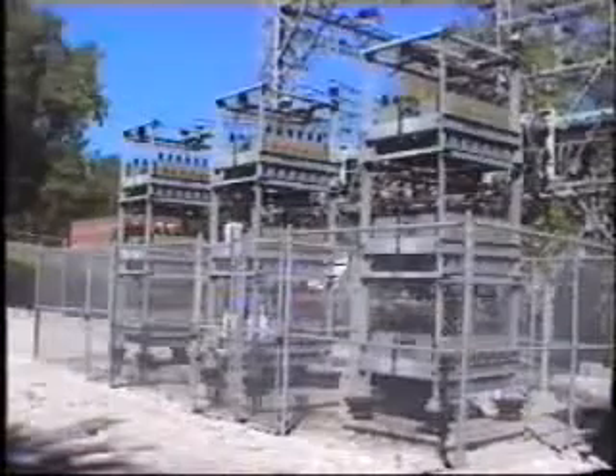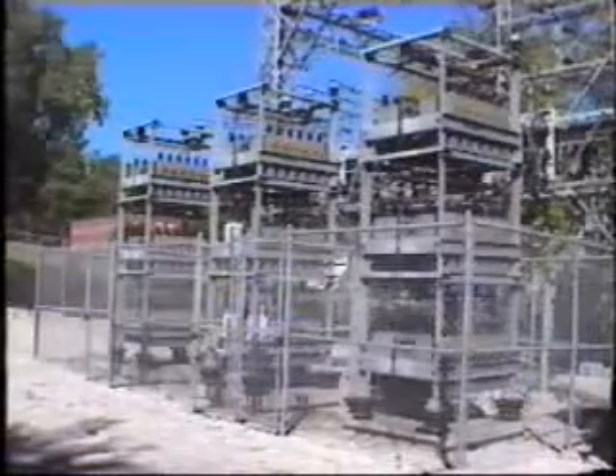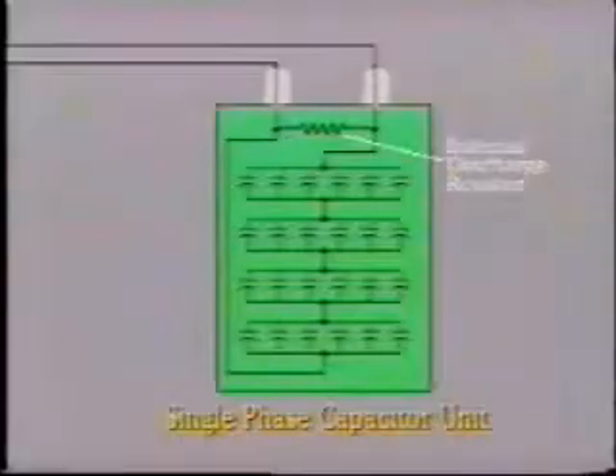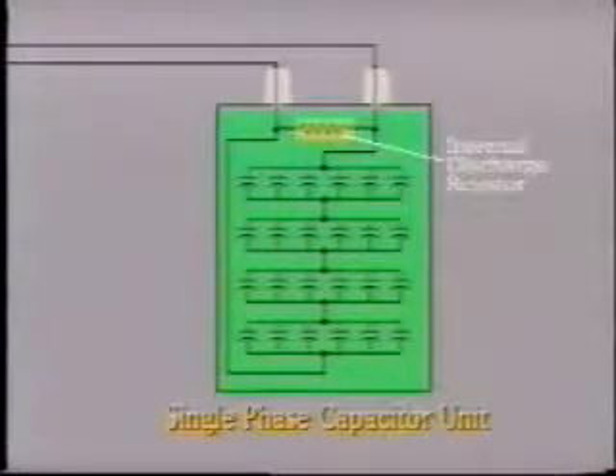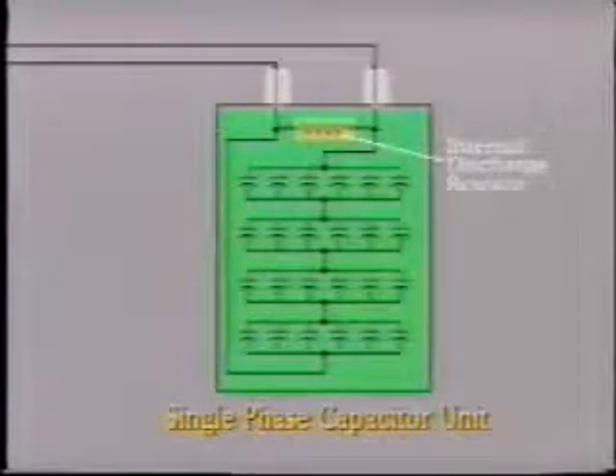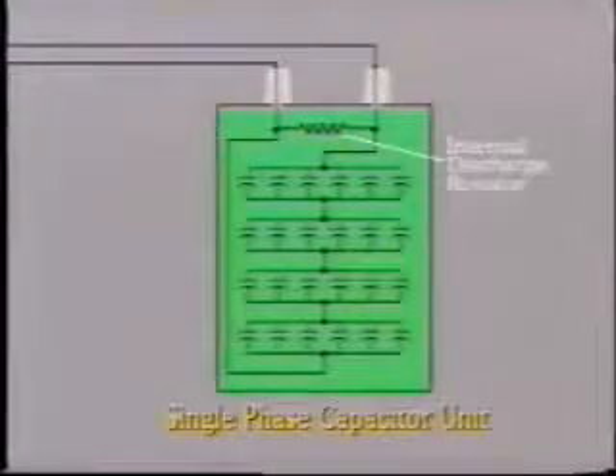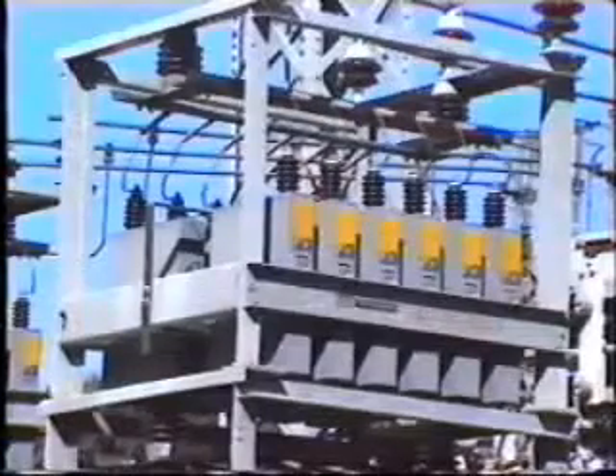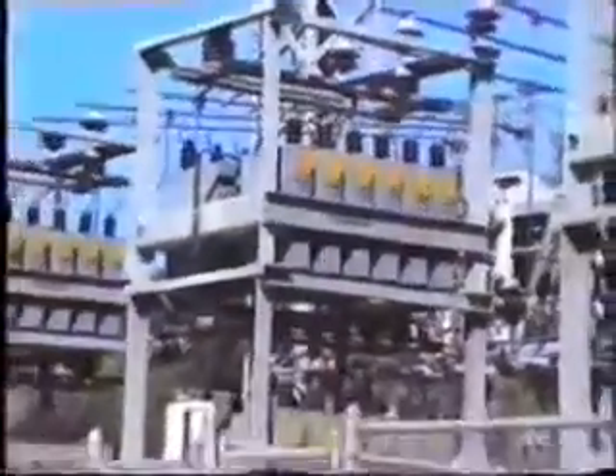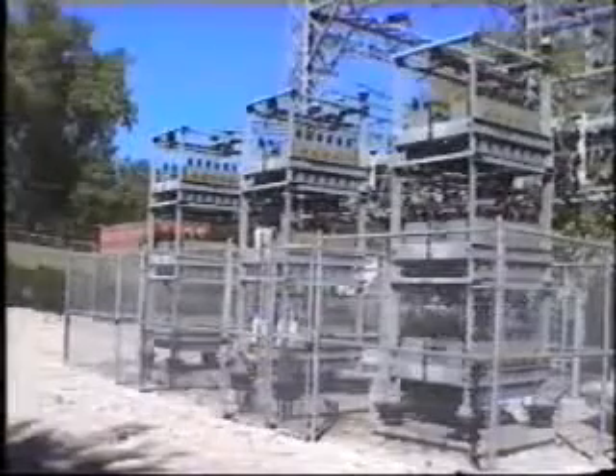In this regard, capacitor banks can be particularly hazardous because of the high voltage and large capacity. In most installations, a discharge resistor is built into each capacitor. When the capacitor is disconnected from the power system, the resistor will discharge the unit down to, say, 50 volts within about 5 minutes. However, be aware. Experience has shown that if the resistor and capacitor are defective, it may result in the capacitor bank and also the supporting metal structure becoming energized. Make sure that you follow your utility's safety rules when working on capacitor banks.